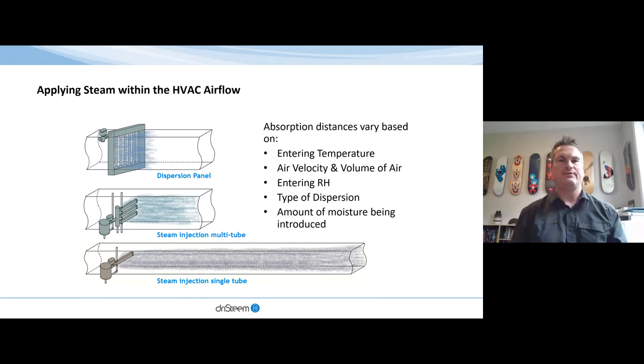If we have a small space or small duct and we're trying to introduce maybe 10 pounds per hour, we might have an absorption distance of 12 inches. But if we have that same small duct and we're trying to introduce 200 pounds an hour of moisture, it may take 14 feet because we're saturating a very small amount of space. So we're introducing a much larger amount of moisture. Those are some of the factors that need to be considered when applying moisture in the airflow.